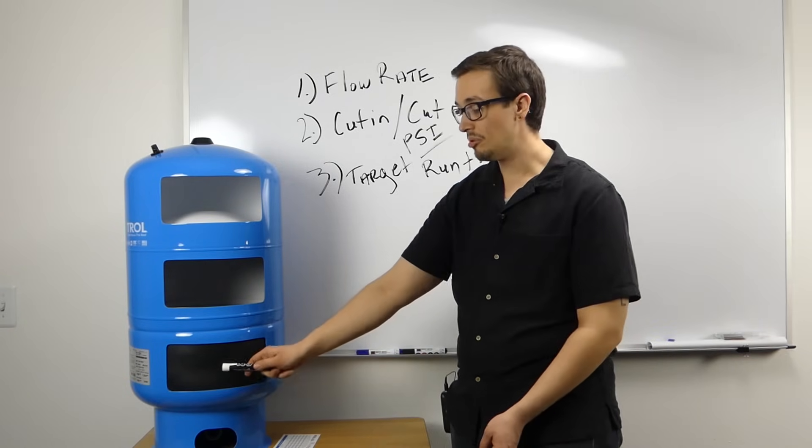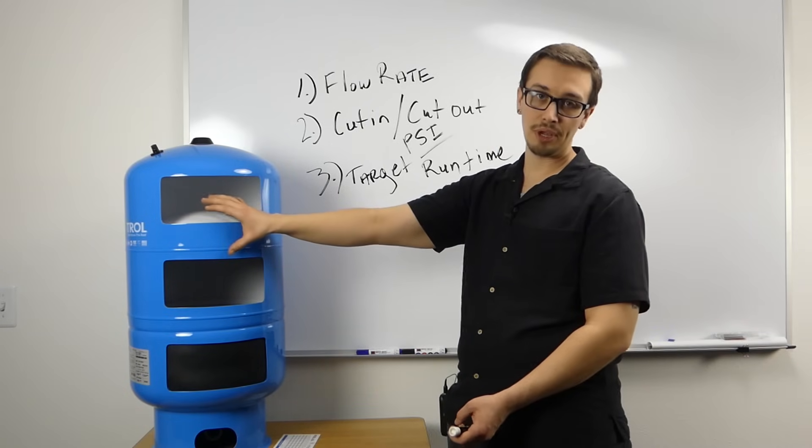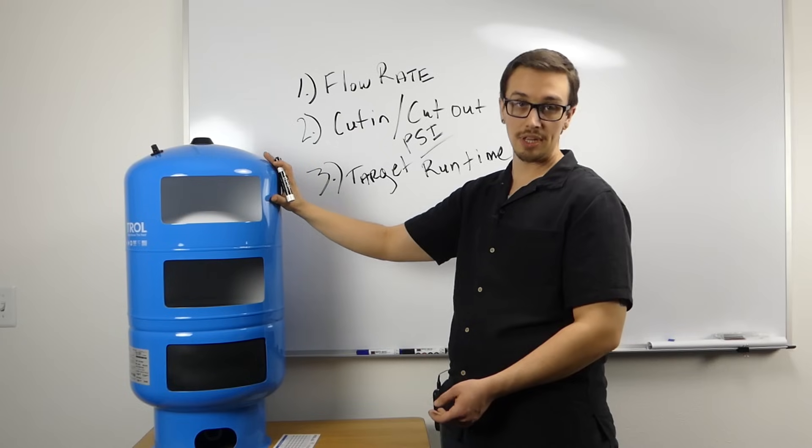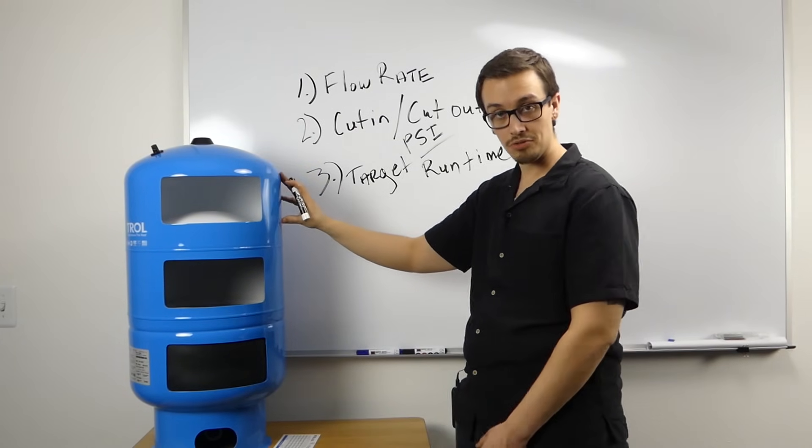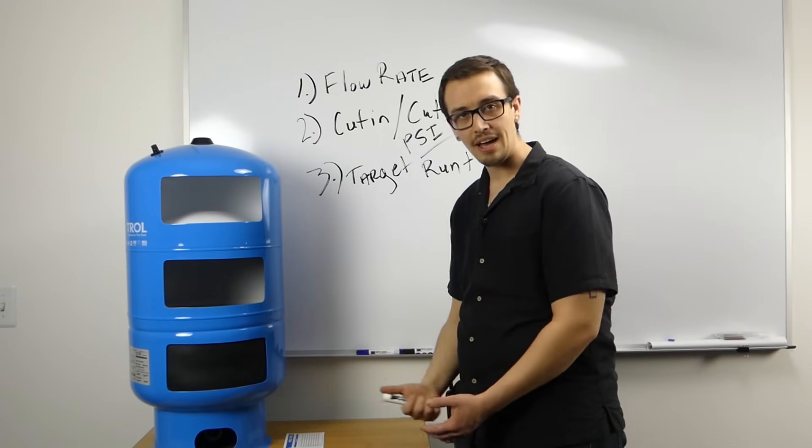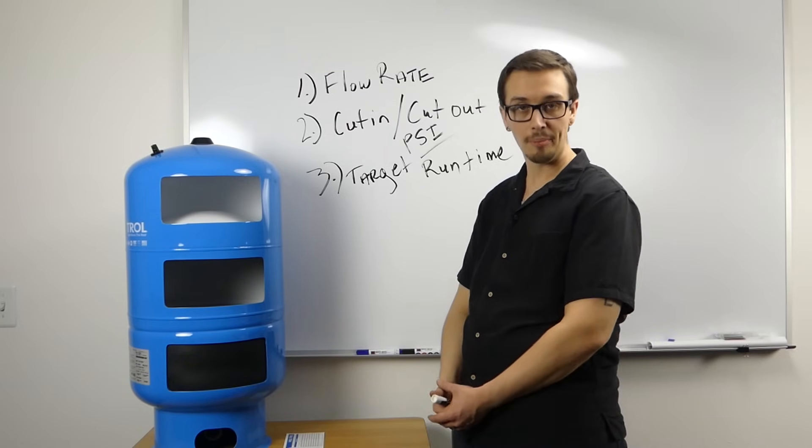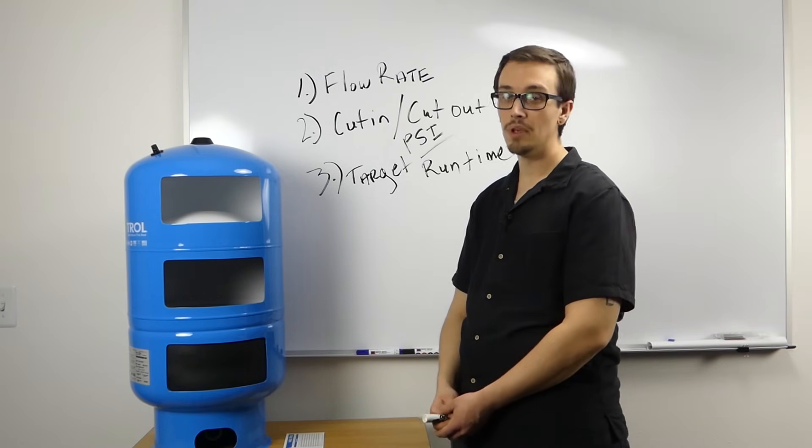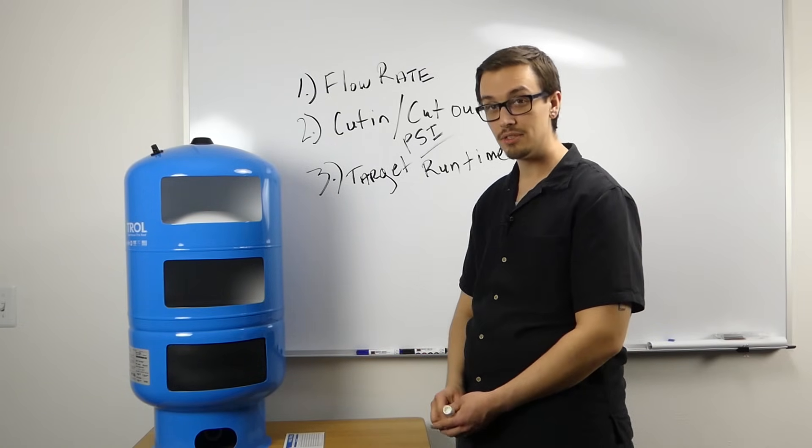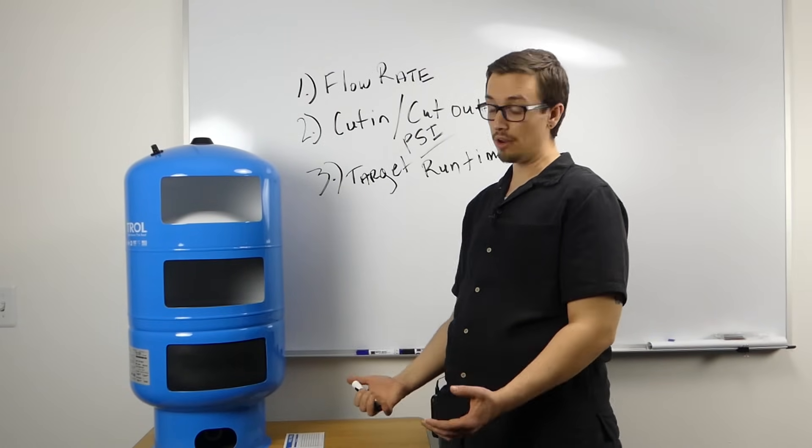You have a bladder in the tank that can only expand so far, and then the rest of the space in the tank is air. In the instance of this 20-gallon tank, you only have a drawdown capacity of about four and a half to six and a half gallons depending on the operating pressure of the system. So a 20-gallon tank only has between four and a half to six and a half gallons, which gives you an idea of the type of cycle time you're going to be looking at.